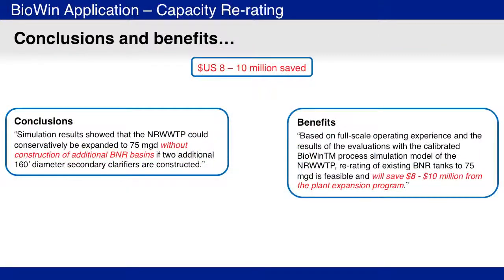Based on the BioWin analysis, it was concluded that the Neuse River Wastewater Treatment Plant could be expanded to 75 million gallons per day with no additional activated sludge basins, as long as two additional secondary clarifiers were constructed. This finding translates to a savings of $8 to $10 million in the plant expansion program.